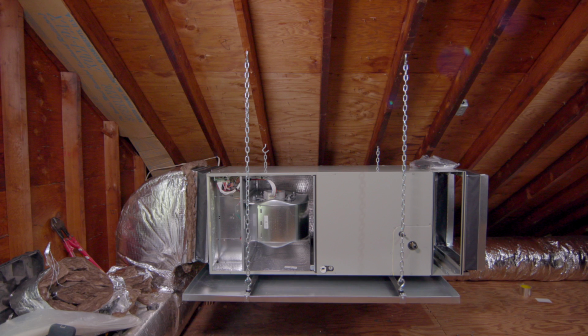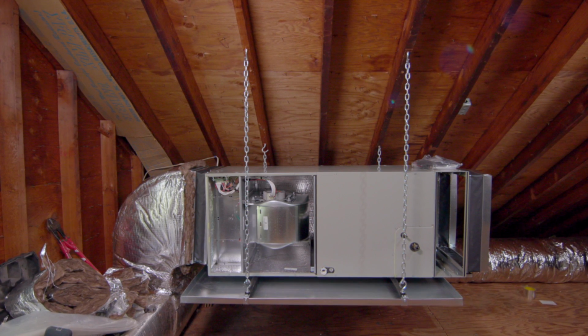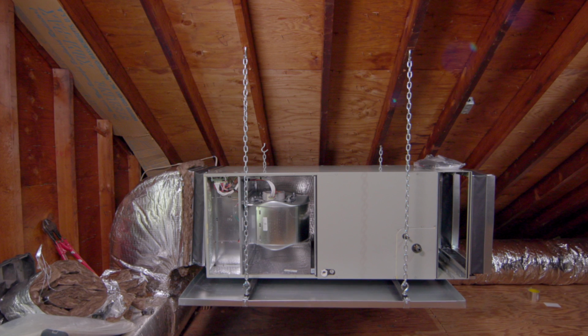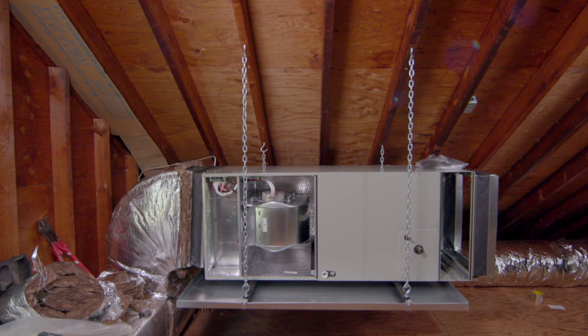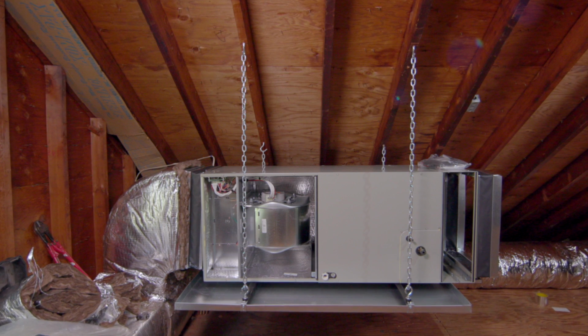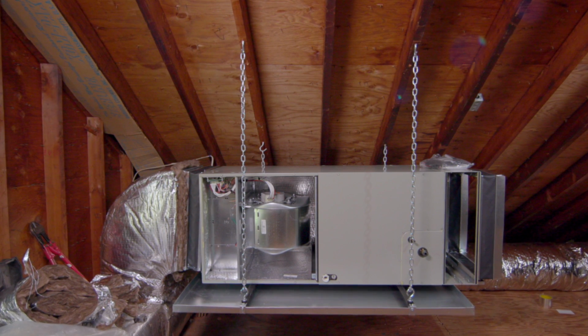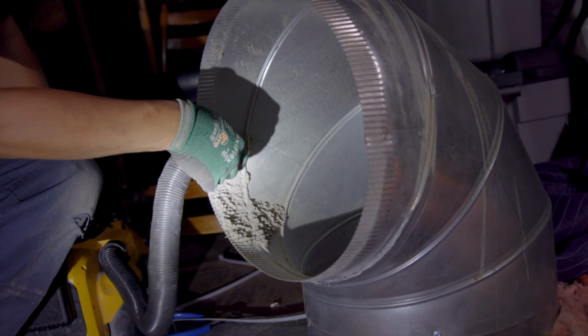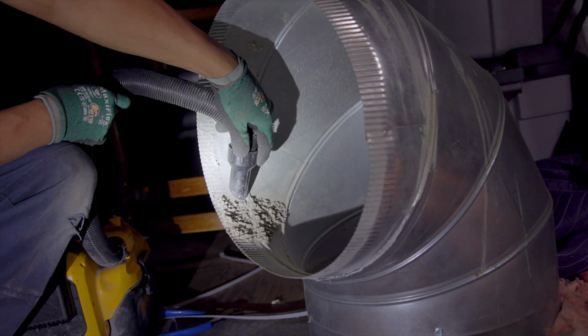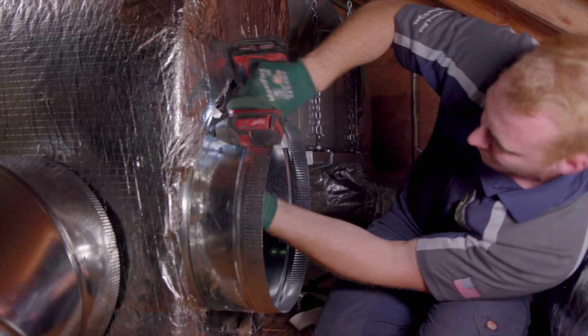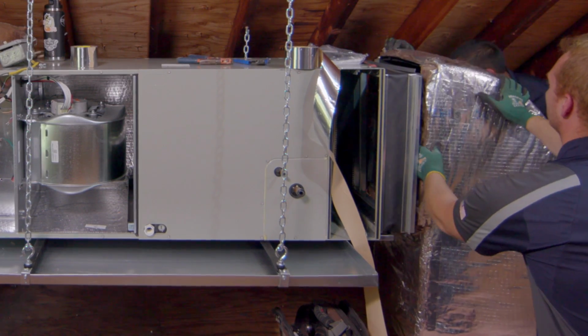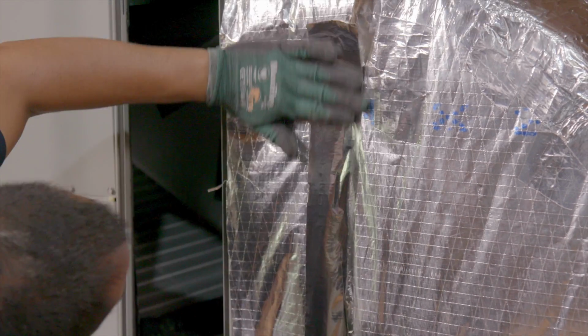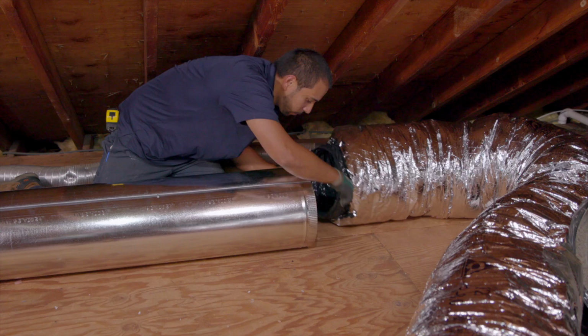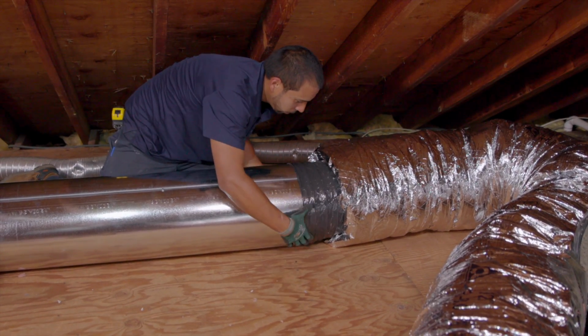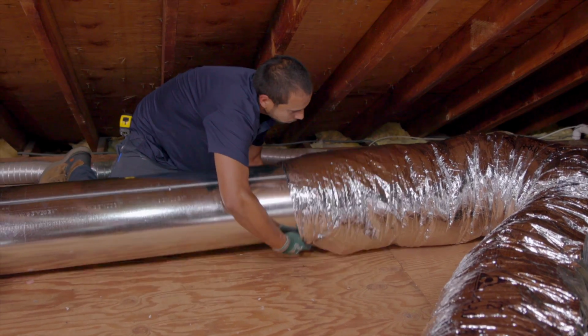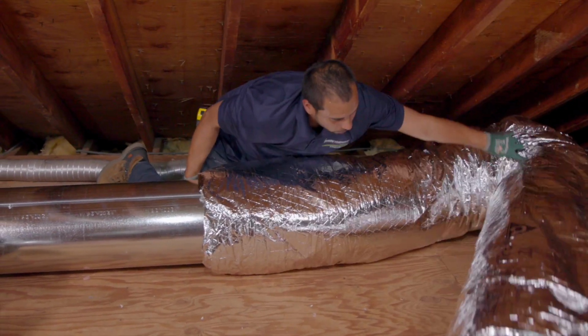In an attic like mine, the air handler is often suspended from the rafters with chain. A professional installation includes a drip pan beneath the air handler to capture condensate and drain it to the ground outside. With the air handler secured in place, Rich cleans the dusty return duct, while Brian installs a couple of new fittings. Then the two technicians begin connecting the ductwork to the air handler and sealing the seams using aluminum foil insulation tape. One of the major flexible supply ducts is replaced with a rigid metal duct with thicker insulation. This will also improve airflow.